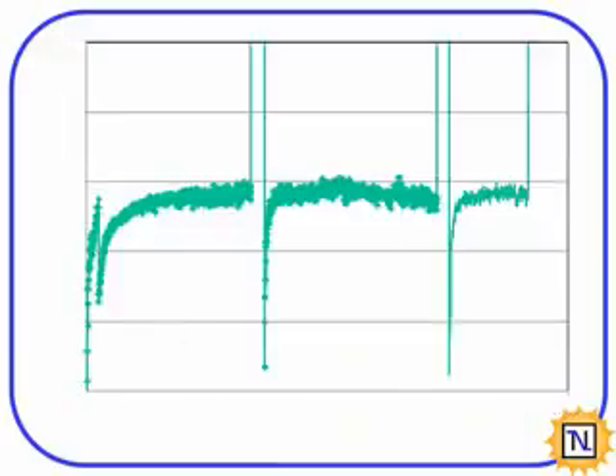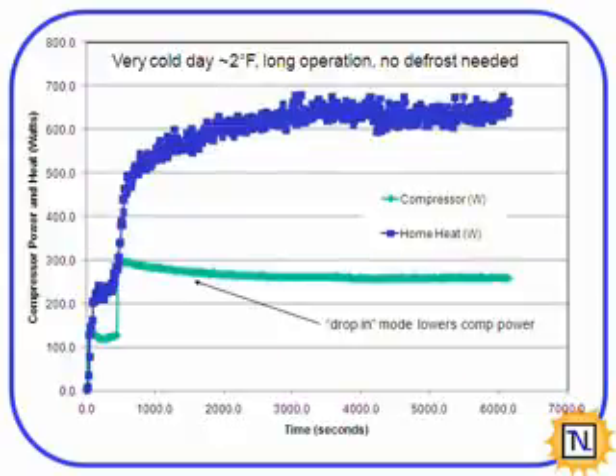Here's the coefficient of performance. And here's another day. This day's pretty cold, and this is newer data from the past few weeks, and it's been good as far as testing the system. So we see the compressor power dropping here. That's a function of this drop-in mode control. The compressor we're using has its own control right now. We'll be developing our own control algorithm. The maximum is about 400, so we'd probably be up there in this case, but as it is, it's adjusting and doing its own thing. We're getting about 250 here and just over 600 watts of heating capacity.